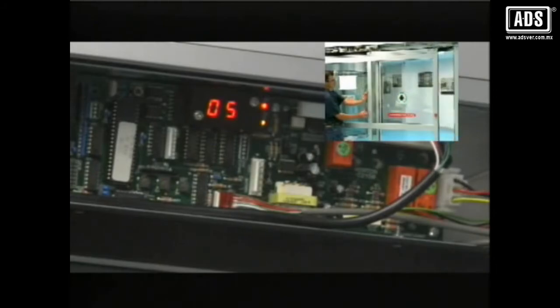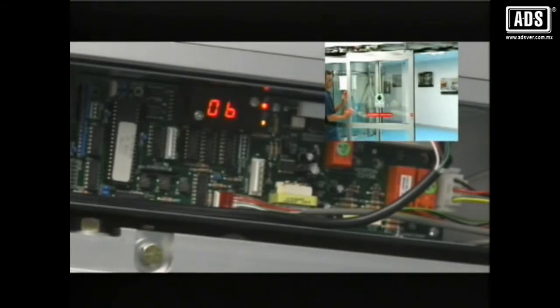OB is the opening obstruction parameter. The C2150 samples the pulse rate every quarter of a second during opening. If the door encounters an obstruction, the pulse rate will slow. Sensitivity to this change is selected by a 0 to 3 parameter. Factory default of 3 is the most sensitive and 0 is off.